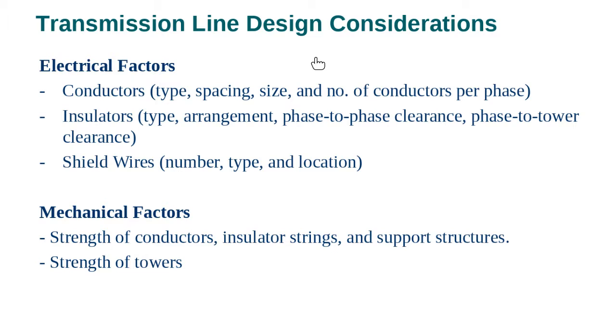So what you see is aluminum, and we'll come to why aluminum is used - because it is light, instead of having copper. But in underground cables, they are made of copper. Copper has higher conductivity, so fewer losses, but it's okay to have more losses with aluminum - this is the compromise of design. Losses in aluminum are okay, but it is light, and we want something light. It's very light - if you carry it like this, you can carry it, you will barely feel the weight. You will see very small, very light conductors when you have a transmission line, like this 132 kV example.